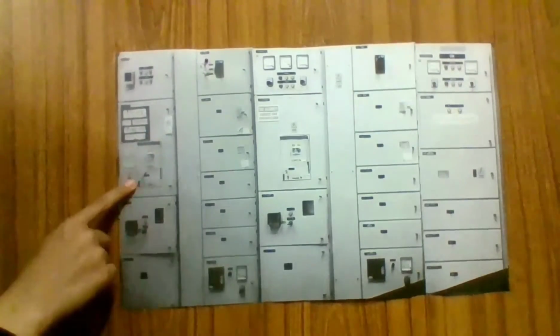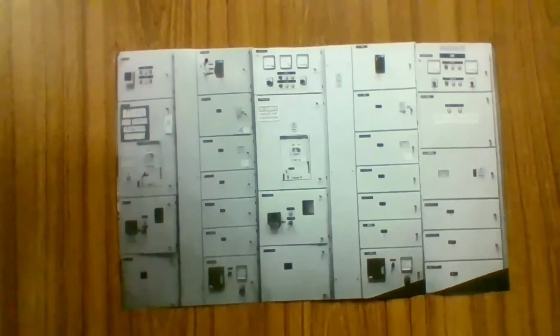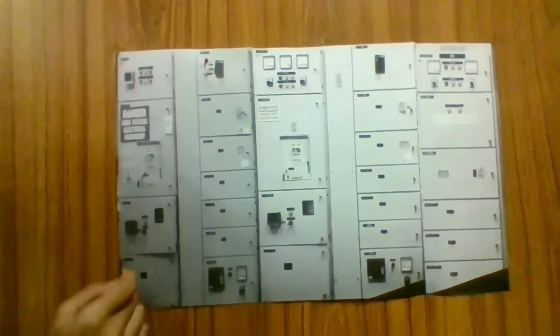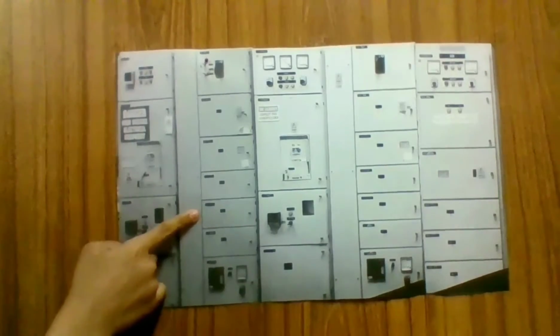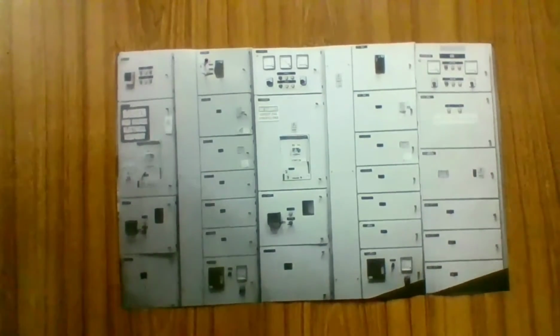First, we need to take out the ACB for maintenance purpose. To do this, first turn off all the loads at MSB1, starting with the load with small rating power to the load with bigger rating power. But before that, we need to inform the consumer that the power supply is going to be cut off.